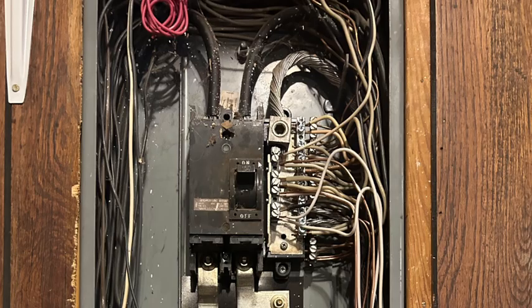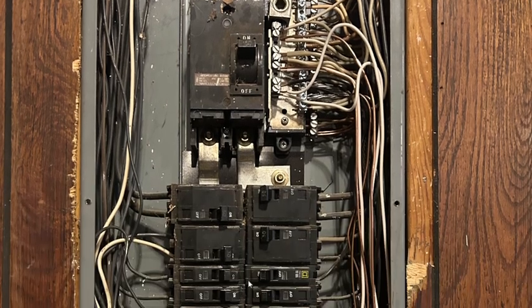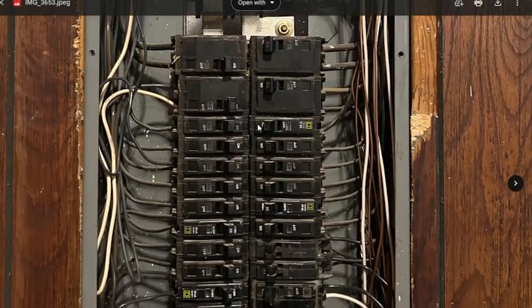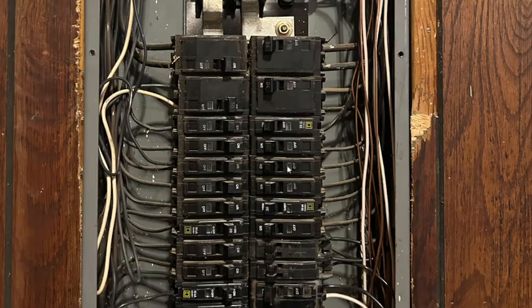All right, these are all our neutrals and grounds. So if you can see, yes, this panel is full. Look at all my single pole breakers. All of those little single poles are for branch circuits. This is a 2-story house, very big house. Probably most of them are for either the general lighting loads, small appliances. There's going to be a laundry circuit in here, a couple of circuits, one for the garage and things like that. All the ones that we're talking about right now.